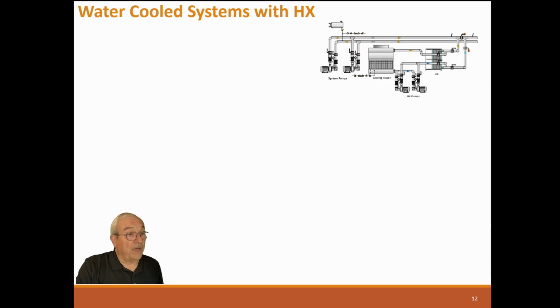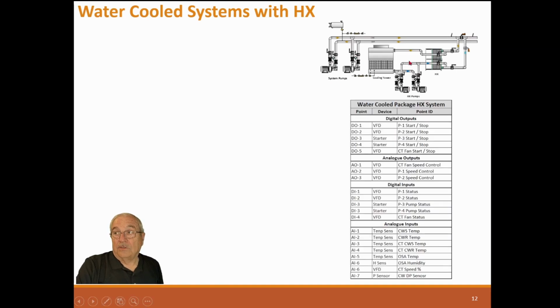But if you have to change the fluid cooler every 10 years, this cooling tower here on a 100-ton system might be $5,000. A 100-ton fluid cooler might be $25,000. So it could be a huge difference. So this was very popular because I could reduce the energy consumption of the system by 30%. It's a large saving in energy, and this paid for itself very quickly. So what happens is we just use a standard cooling tower, and we'll go through that to look at it. So standard cooling tower, heat exchanger.